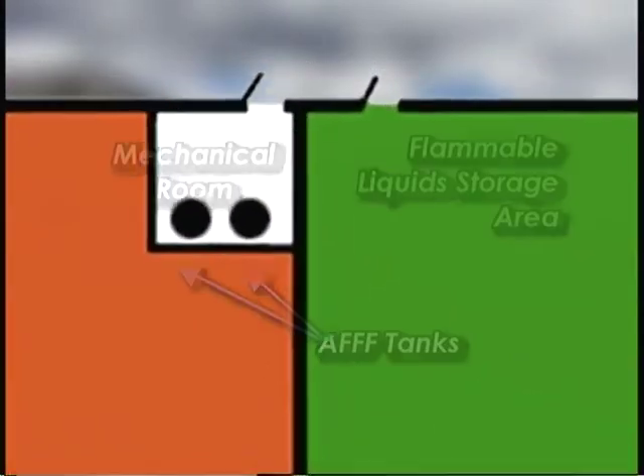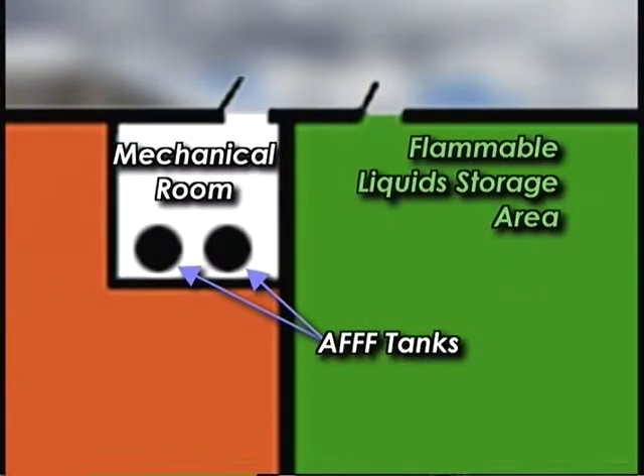An aqueous film-forming foam, or AFFF system, provides coverage for the flammable liquid storage area. The AFFF tank and associated valves are located in a mechanical room at the exterior of the building, but central to the location of the flammable liquid storage area. This facilitates shorter foam extinguishing agent release times once a system is activated.